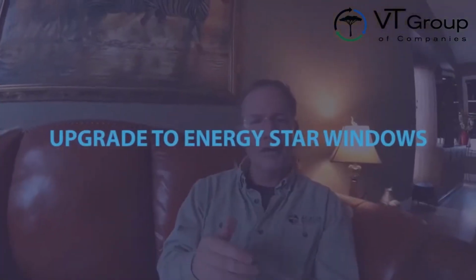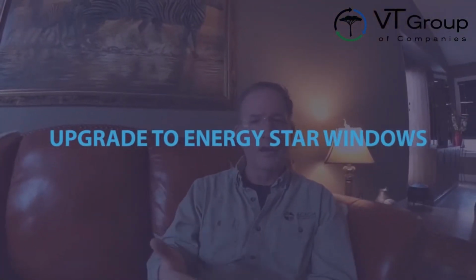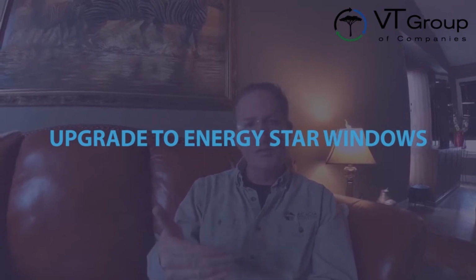Well, there's really only one way to do that, and that is to upgrade your windows. So by putting in a better quality window, ideally a triple pane window with a low emissivity coating and argon gas in between, that's going to give you a warmer surface temperature. Again, with higher humidity, a warmer surface temperature means we are not going to see that condensation. So make sure you think about upgrading your windows.